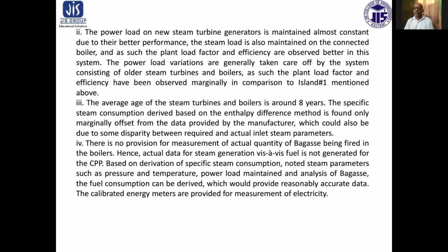There is no provision for measurement of steam generation and fuel that is generated for the CPP. Based on the derived specific steam consumption, noted steam parameters such as pressure and temperature, power load maintained, and analysis of bagasse, the fuel consumption can be derived, which would provide reasonably accurate data. Calibrated energy meters are provided for measuring electricity.